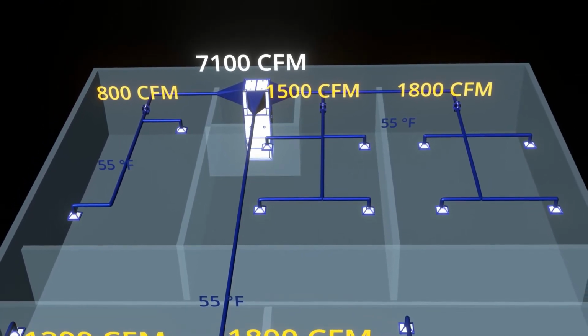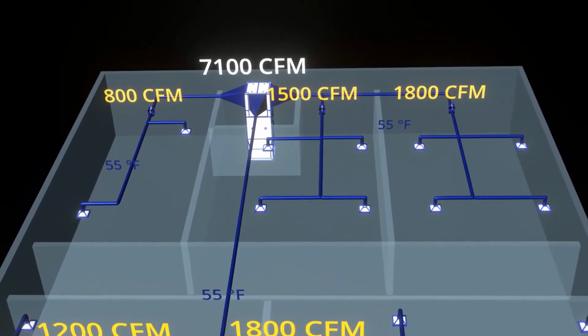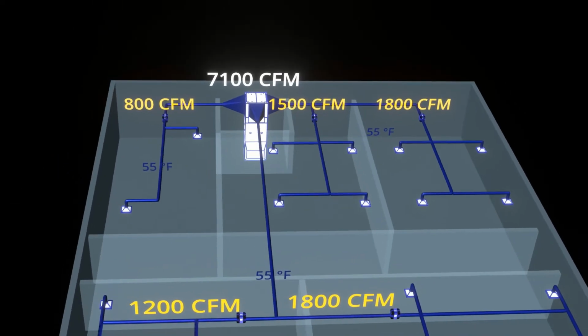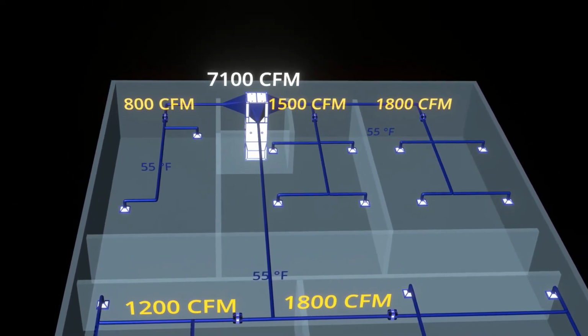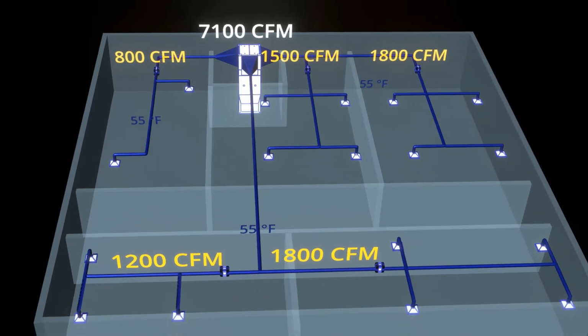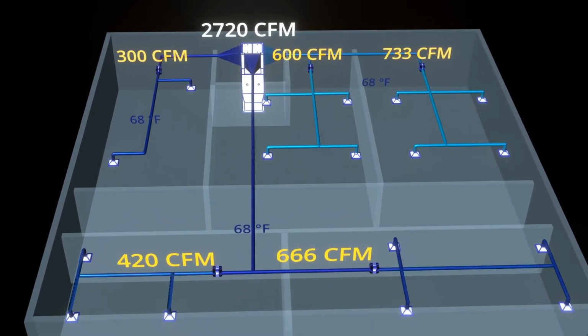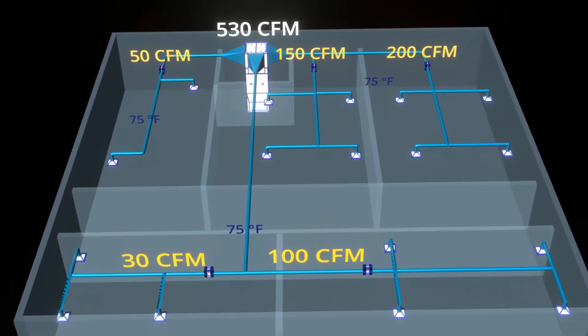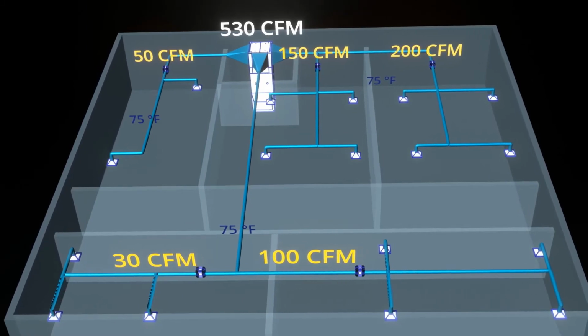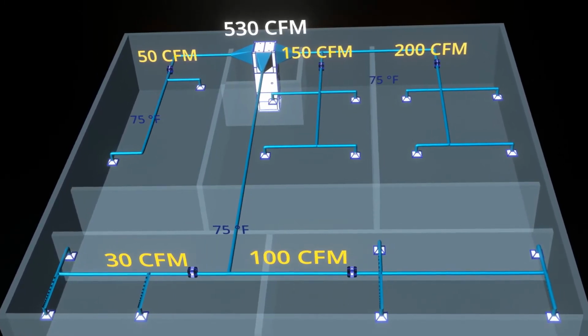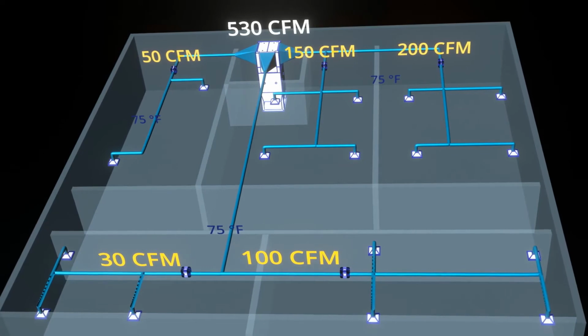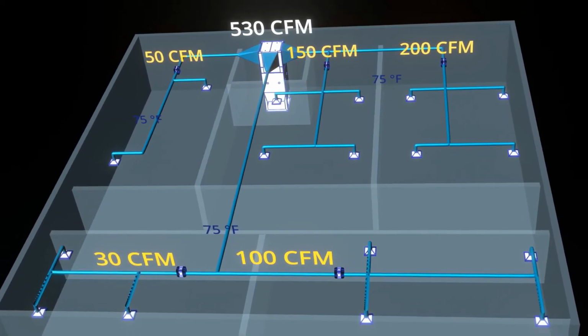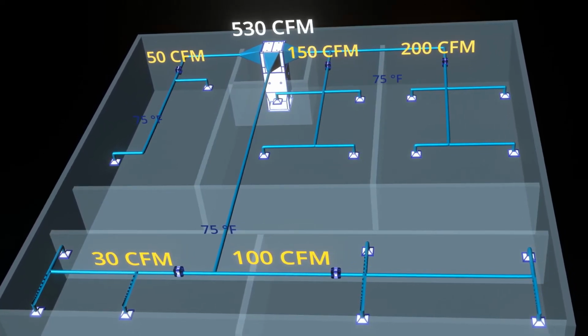The self-balancing SAVs turn the building into one giant calibrated flow stand. This allows for fine-tuning of the building's performance through simple software enhancements. Diffusers and lighting can be relocated without costly mechanical retrofits. The high turndown self-balancing system allows for zone updates commensurate to the FlexSpace's requirements with a simple software input change.